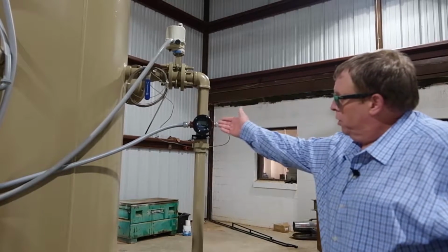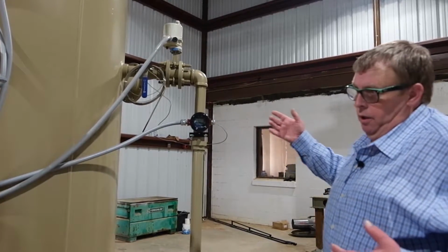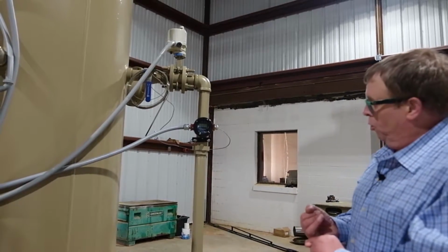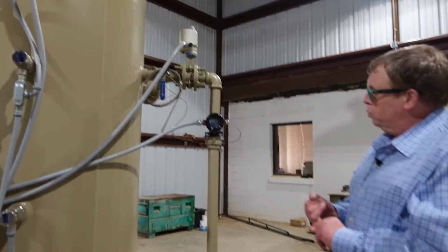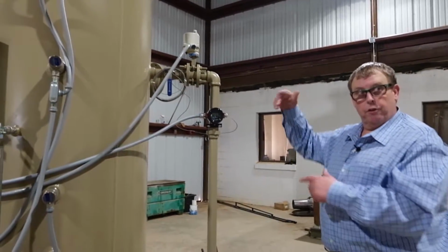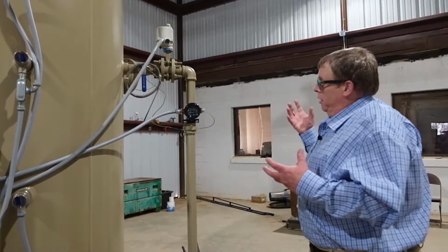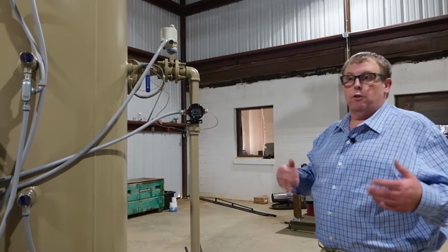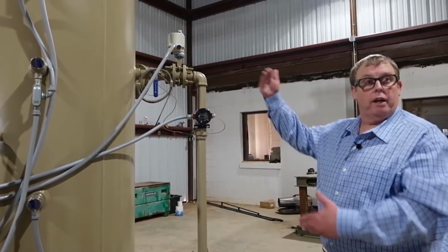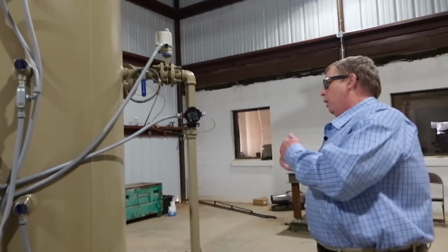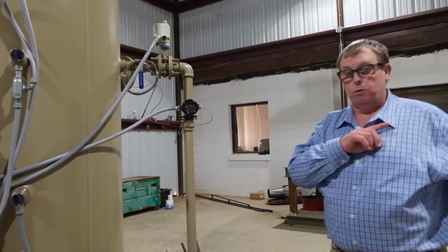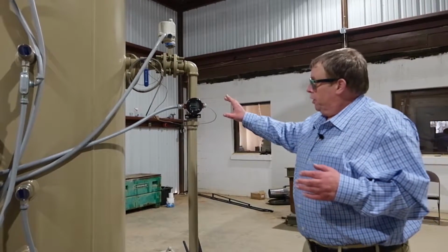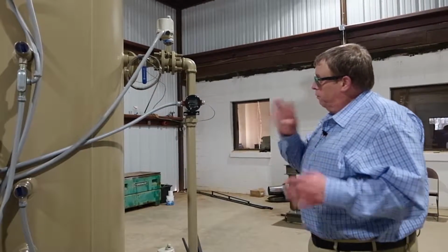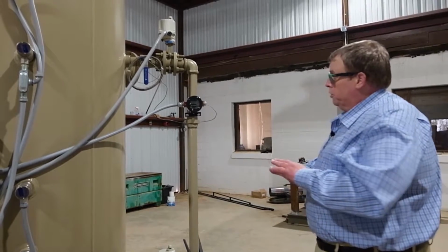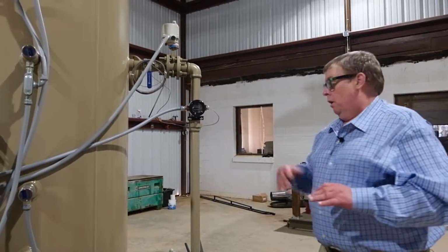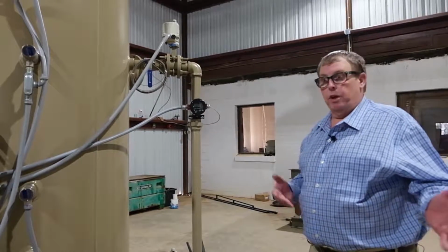However, the Moore transmitter, in this case the one that we've selected, is doing several things here, Todd. One is it's got target controls where you can set a target temperature coming off of your thermocouple probe, and you can use those targets to create a dry contact. Say you want your flare to reignite at a certain temperature, or you're wanting to send that communication out to the SCADA like we said earlier. This particular unit has the ability of 4 outputs. So you can have a Modbus, or you can have a 4 to 20 milliamp output. Very friendly to the automations guys. We hear that they like it.